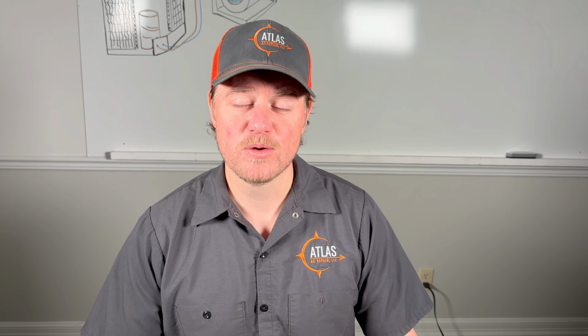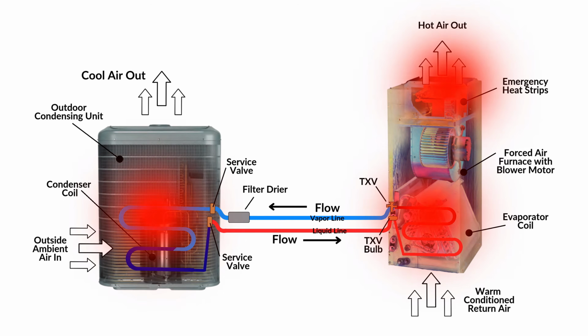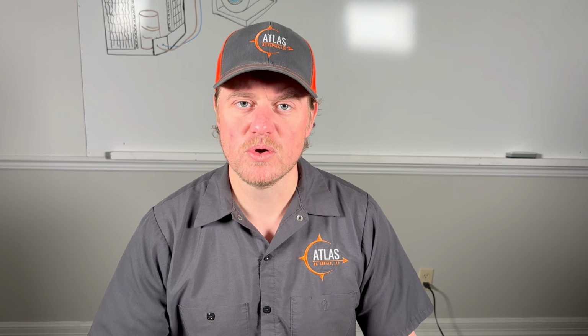The next type was supplemental heat, when it got cold enough for the system to no longer be able to satisfy the thermostat temperature. It then used the heat pump and the heat kits at the same time in order to give it a little bit of a boost. It can also go into this mode if I raise the thermostat temperature, let's say by 5 or 6 degrees, and the heat pump knows that it can't satisfy it very quickly. It will also use supplemental heat to help speed things along. And a quick tip that's especially true when it comes to supplemental heat, make sure that your filters are good. That way it doesn't mess up the heating operations of the system. So if you know a cold snap's on the way, make sure you check your filters.